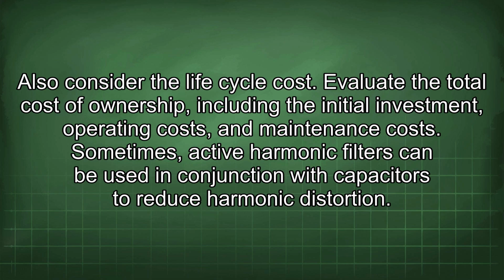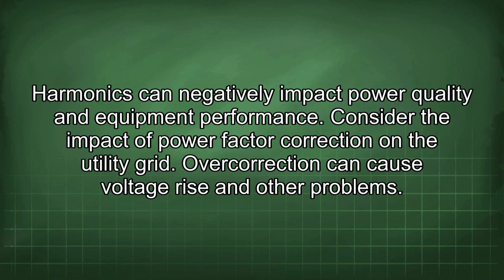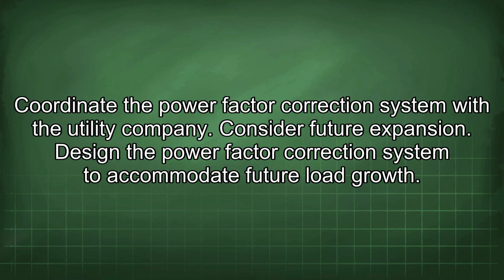Sometimes active harmonic filters can be used in conjunction with capacitors to reduce harmonic distortion. Harmonics can negatively impact power quality and equipment performance. Consider the impact of power factor correction on the utility grid. Overcorrection can cause voltage rise and other problems. Coordinate the power factor correction system with the utility company. Consider future expansion. Design the power factor correction system to accommodate future load growth.